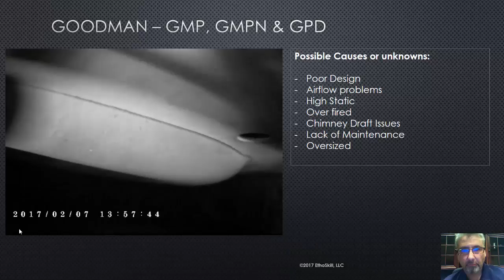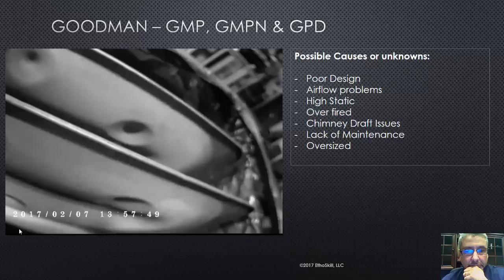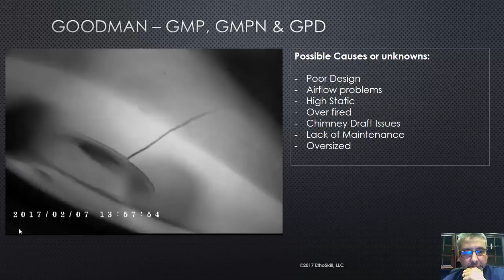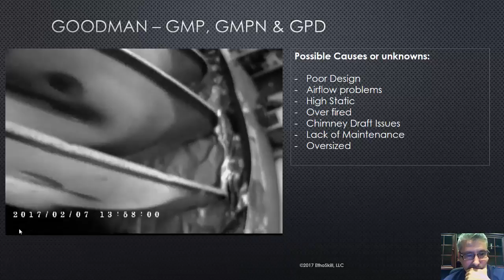So again, just a quick recap: you've got the dimples, watch the dimples, right here you want to watch those dimples. You can see again that one. Watch your rings on both sides, check the rings. And then wherever the heat exchanger curves, like right there. So there you go, there you have it on the Goodman 80 percenters, the older ones, what to look for.